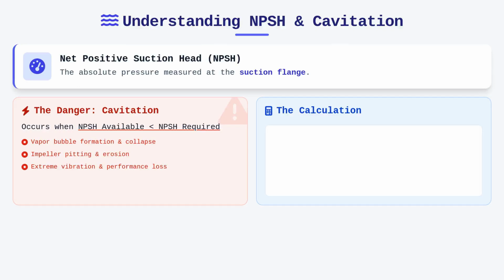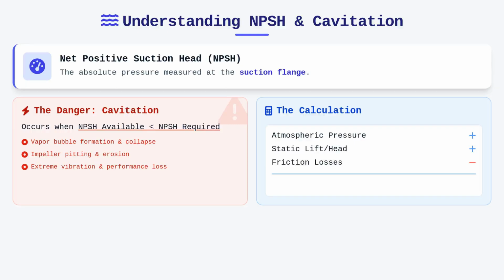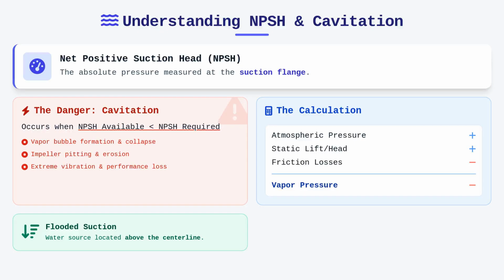To calculate this, one must account for the atmospheric pressure, the static lift, or head, and the friction losses in the suction piping while subtracting the vapor pressure of the water. Ensuring the pump has a flooded suction, where the water source is located above the pump centerline, is the most effective way to eliminate these suction side pitfalls. In scenarios where a vertical turbine pump is deployed in an underground reservoir, we are effectively utilizing a column-supported impeller design to satisfy these hydraulic requirements from the bottom up.